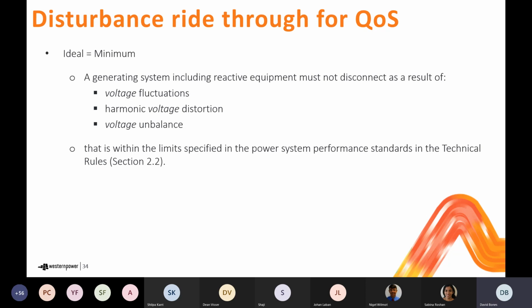And while this specific ride-through requirement is not expressed in this particular way in the current technical rules, it is captured somewhat by a general obligation on all users to ensure their facilities are capable of operation within the system performance standards specified in section 2.2. So that's the existing rule in clause 321A of the technical rules. So what we're thinking is that the inclusion of this additional disturbance ride-through requirement provides a bit more clarity, but really doesn't add any additional burden on large generators beyond what they would have faced under the existing technical rules.